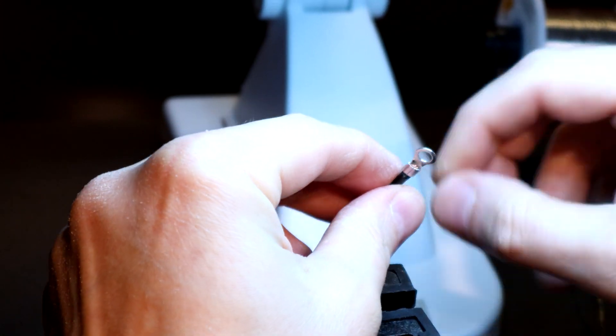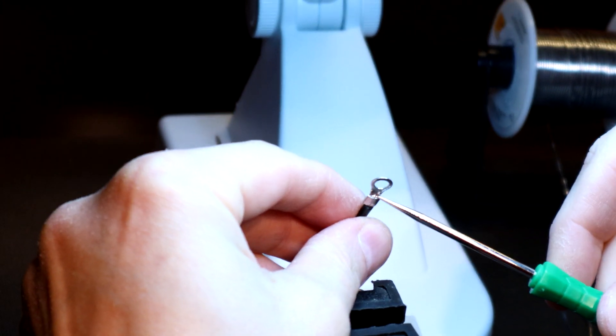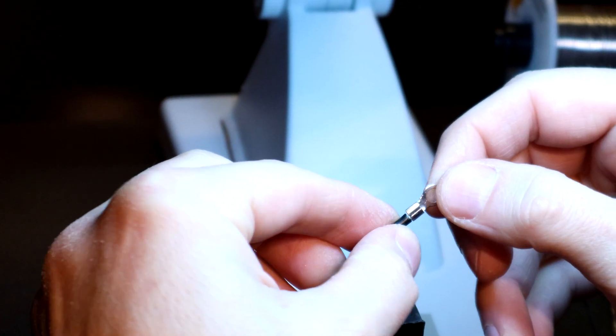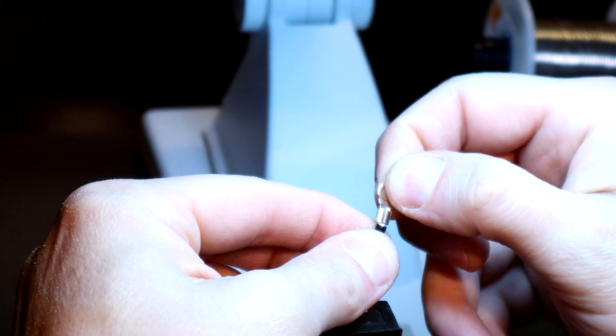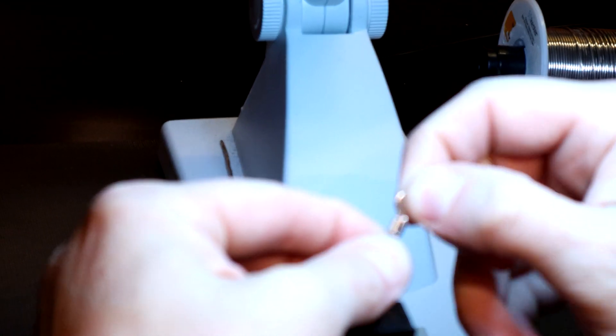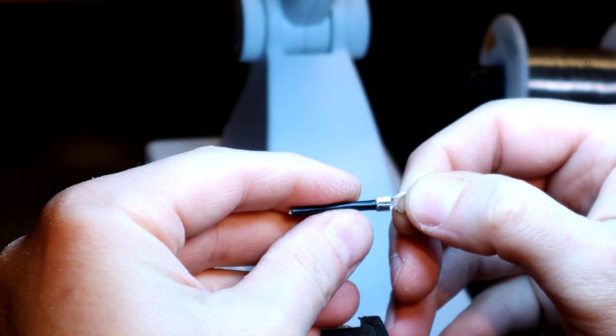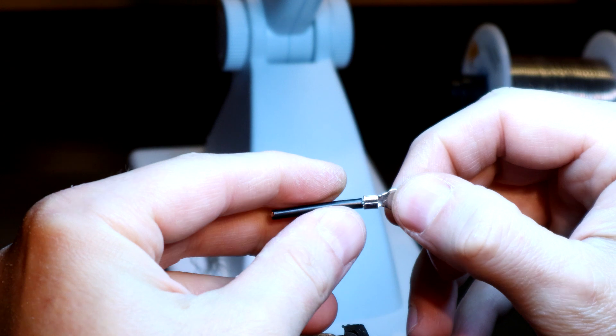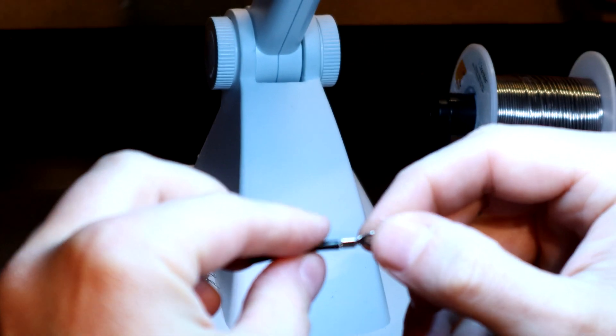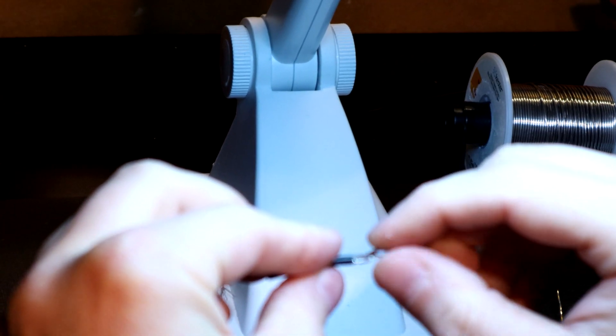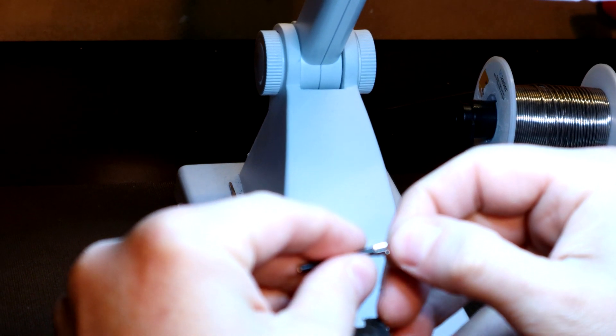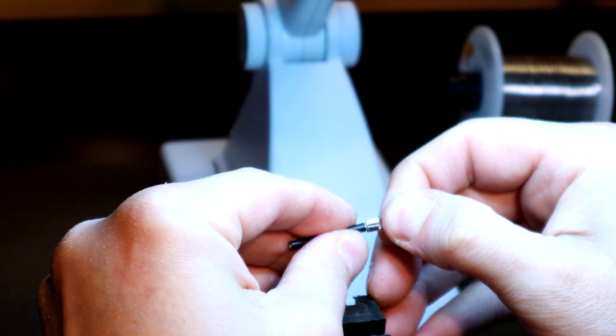It's done perfectly. You can see here we've got our crimp in there. We've got our conductors inside here. You can see how they're all non-bound. If we flex this, and this is why I'm not fond of crimp connectors, look at this. Now let me show you something. This is really interesting. Watch what happens. This is crimped. This is crimped with the crimping tool. You can see it was done perfectly. Look at the pressure on. It's perfect. It's even. Watch what happens when I pull a little bit.